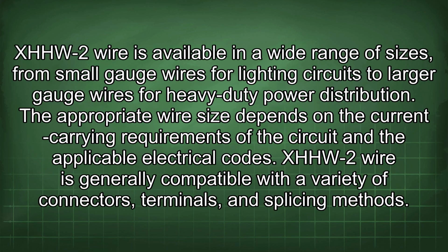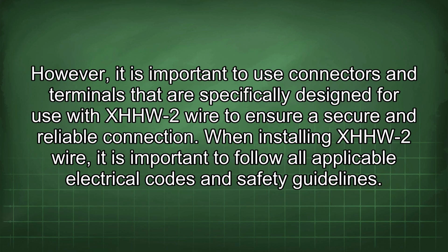XHHW-2 wire is available in a wide range of sizes, from small gauge wires for lighting circuits to larger gauge wires for heavy-duty power distribution. The appropriate wire size depends on the current carrying requirements of the circuit and the applicable electrical codes. XHHW-2 wire is generally compatible with a variety of connectors, terminals, and splicing methods. However, it is important to use connectors and terminals that are specifically designed for use with XHHW-2 wire to ensure a secure and reliable connection.